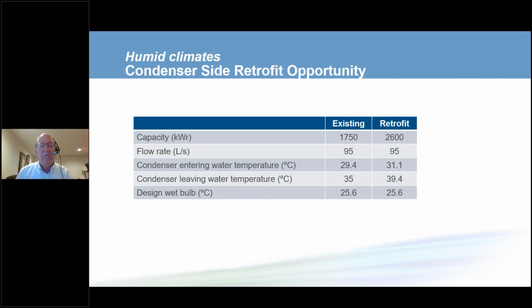But what I tell people is this isn't free this time. Well, we have the same pipes and the same pumps and they're designed for a good condition. In this case, the condenser leaving water temperature went up significantly and the chiller power will go up more than it would on a new job. So you do have to balance this, but many times I've seen jobs come back into budget and be able to move forward because all we had to do was replace the chiller and select it at the proper conditions.